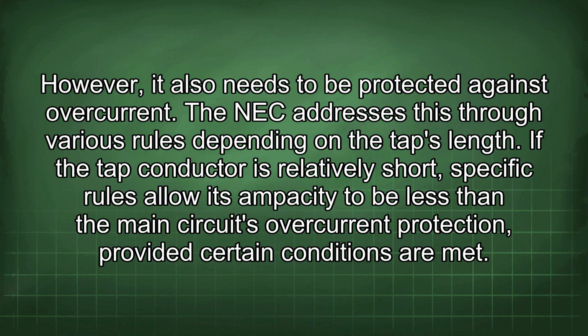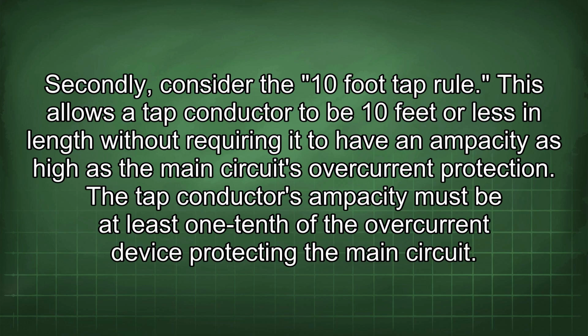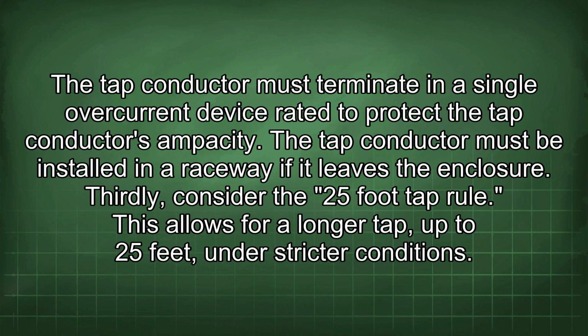The NEC addresses this through various rules depending on the tap's length. If the tap conductor is relatively short, specific rules allow its ampacity to be less than the main circuit's overcurrent protection, provided certain conditions are met. Secondly, consider the 10-foot tap rule. This allows the tap conductor to be 10 feet or less in length without requiring it to have an ampacity as high as the main circuit's overcurrent protection. The tap conductor's ampacity must be at least 1/10 of the overcurrent device protecting the main circuit. The tap conductor must terminate in a single overcurrent device rated to protect the tap conductor's ampacity. The tap conductor must be installed in a raceway if it leaves the enclosure.